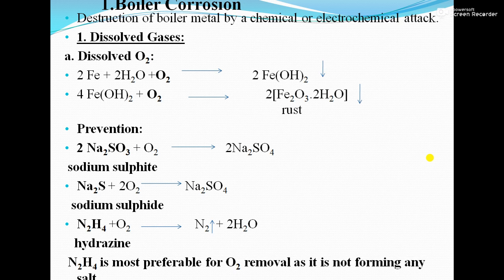First, corrosion due to dissolved gases — the first gas is dissolved oxygen. Fe (iron) is majorly used as boiler metal. Oxygen present dissolved in the water reacts with the boiler metal and forms ferrous hydroxide. If more oxygen is present in the water, that ferrous hydroxide is converted into rust.